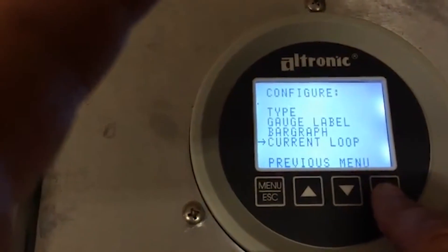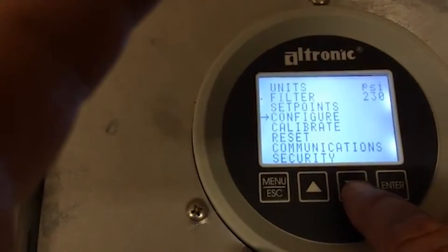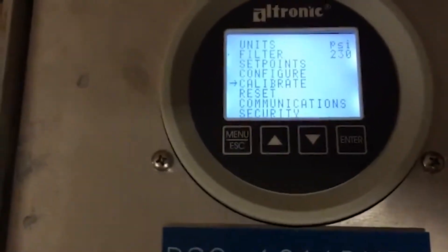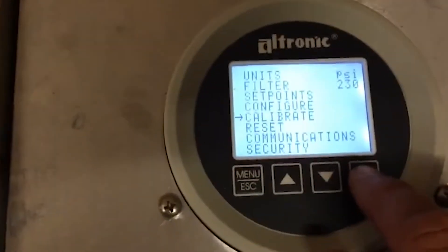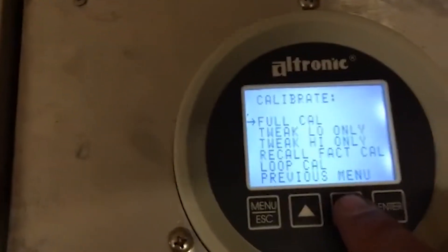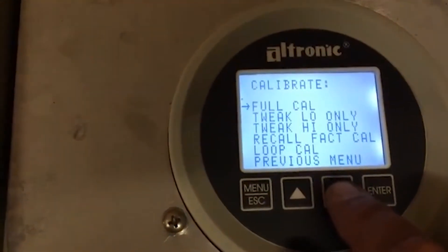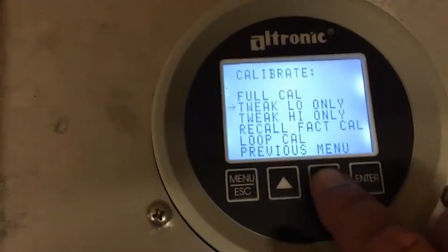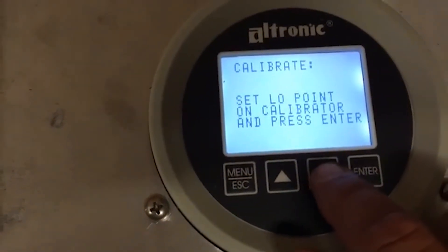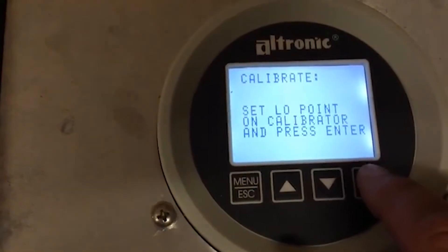Back out to previous menu, then back out one more time. Now go into calibrate. With the pressure transducer open to atmosphere — make sure it's absolutely unpressurized — you cannot do a full tweak unless you have a full set of calibration tools to simulate a full range of pressure. You can do a low tweak, and it's going to ask you to set low point on calibrator and press enter.